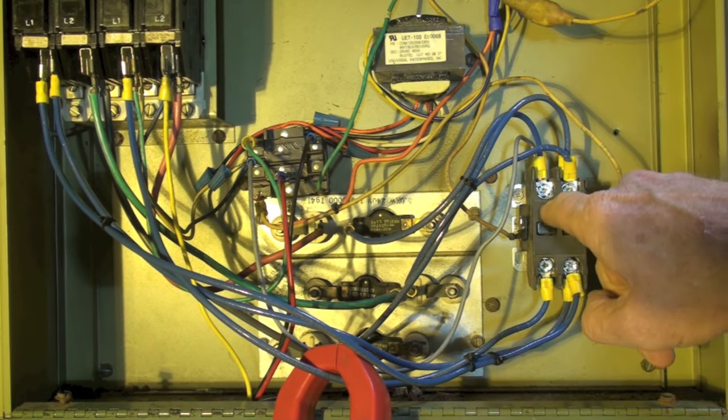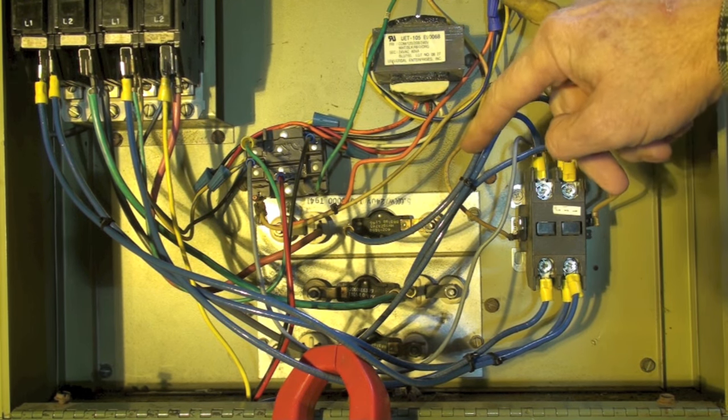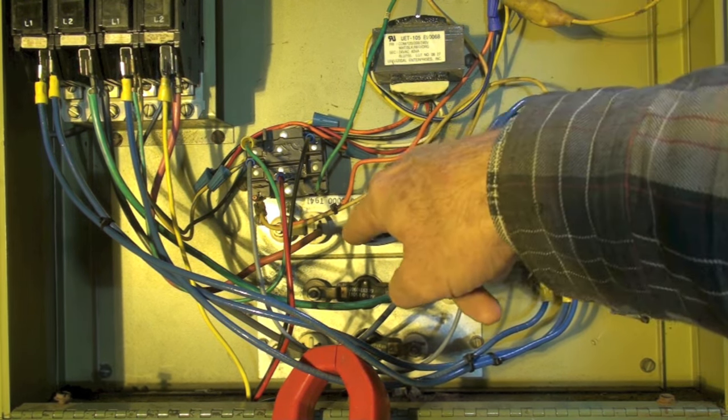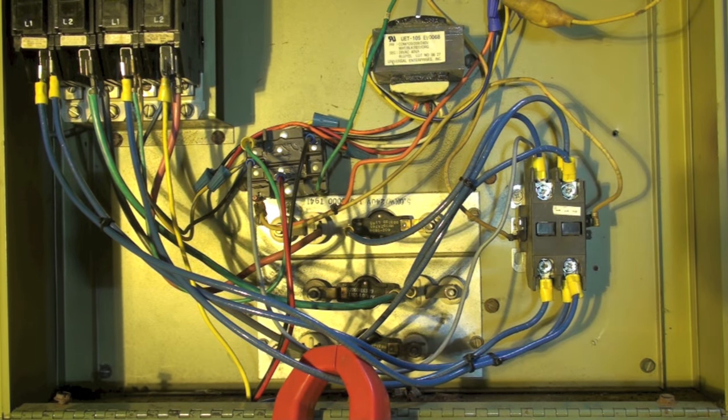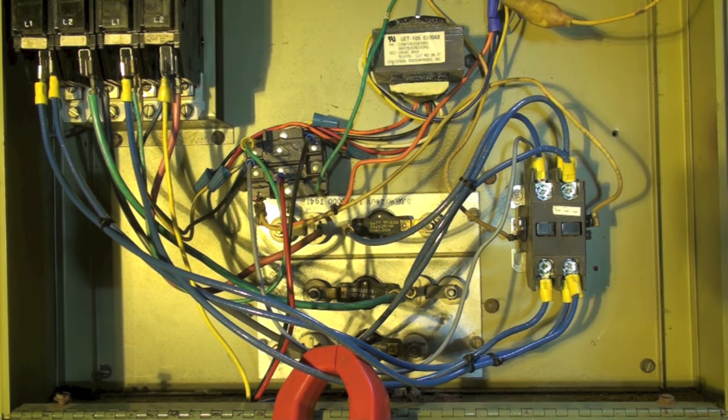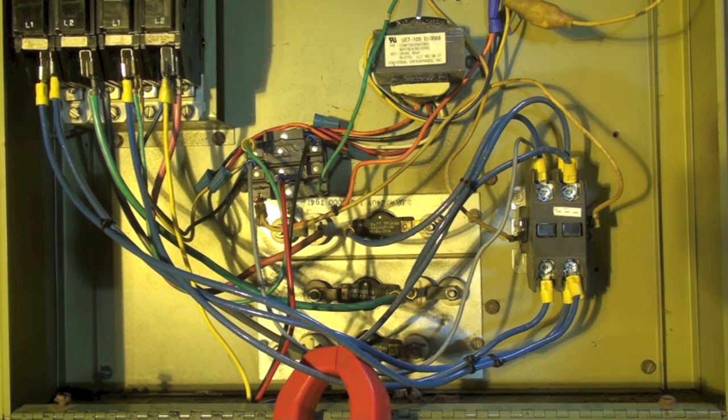So if I follow this out, this is going to this contactor right here that only has one element hooked to it and the power is going to this element. So I'm going to see if I can use my meter to troubleshoot this. I'm going to use a voltmeter now.